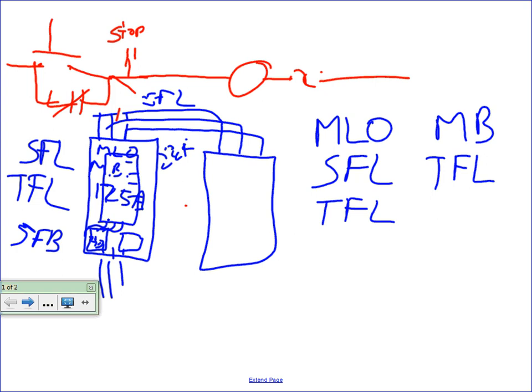Like QO breakers are rated for 10K. Well, we actually have series ratings depending on what the main breaker upstream is that are good up to 65K, because that main device is rated for 65K. These breakers are rated 10K, and we actually shoot that combination with 65,000 amps of fault current. And what happens is that the main reacts much faster than the smaller branch breakers. By the time these branch breakers start to act, the main has pretty much taken out most of the arc from the fault, so that we don't have things exploding within the panel board, okay? And we have to do all that testing for these combinations with UL. If the breaker burns, or if a wire falls off, or anything like that because it stresses the fault current, we fail the test.